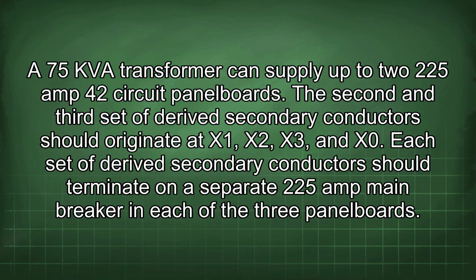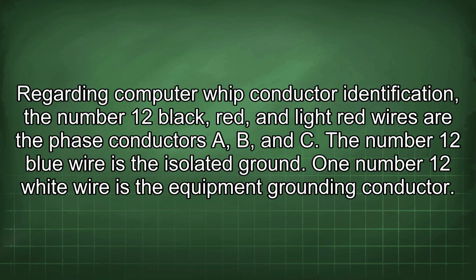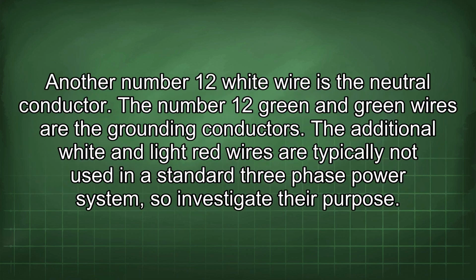Regarding computer whip conductor identification, the number 12 black, red, and light red wires are the phase conductors A, B, and C. The number 12 blue wire is the isolated ground. One number 12 white wire is the equipment grounding conductor. Another number 12 white wire is the neutral conductor. The number 12 green and green wires are the grounding conductors. The additional white and light red wires are typically not used in a standard 3-phase power system, so investigate their purpose.